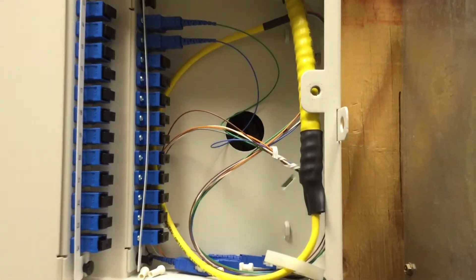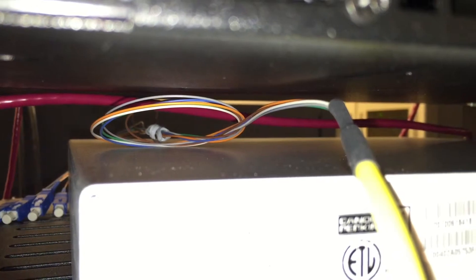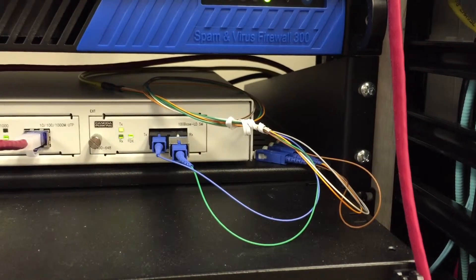This end is in a fiber distribution panel at the DMARC and it's pretty well protected as long as you're not working within this panel. At the other end in the server room, it's a different story. As it enters the rack, the armored jacket is stripped off. Then as it enters the shelf, the next layer is stripped off exposing the bare fibers. Now this is a restricted environment being in the data center, but the fibers are still very exposed for people working on the surrounding equipment.